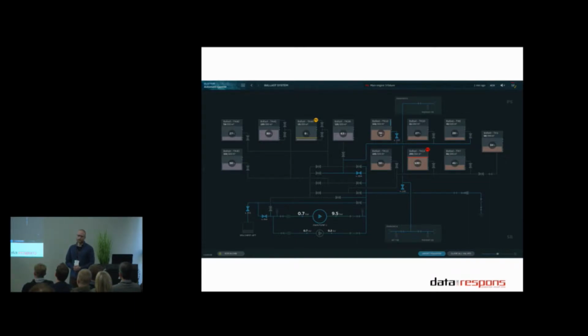Let's say the boat has several tanks filled with gas. You want to keep track of how much is in each tank. You want to be able to open and close valves to control this, and maybe you want to pump, like here. Pump here, valves everywhere, and tanks with a percentage of usage. The signals that are important here are tank levels, alarms, valves, pumps, etc. For instance, the yellow P2 there means it's an alarm, because it's a low level, and then you have P1, which is too high a level on the tank.